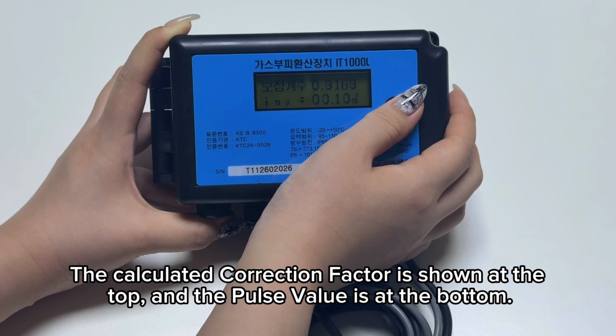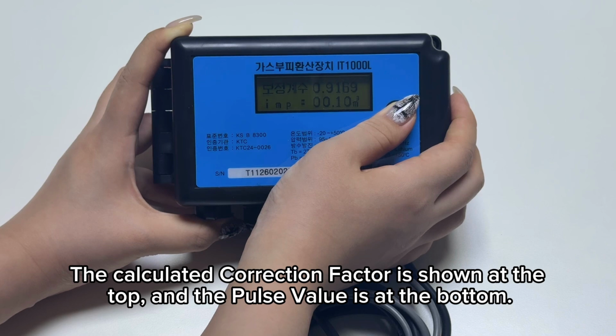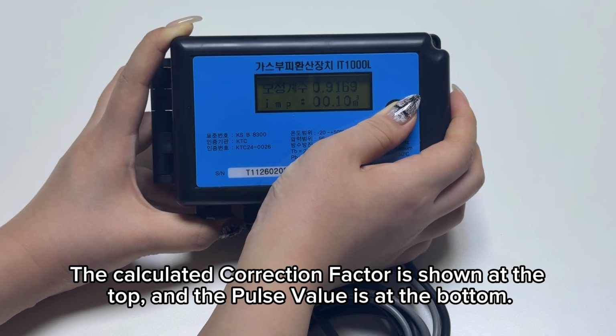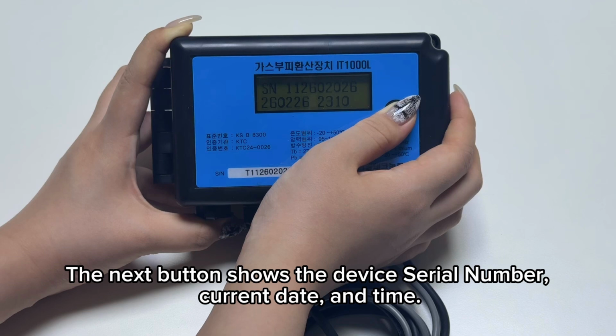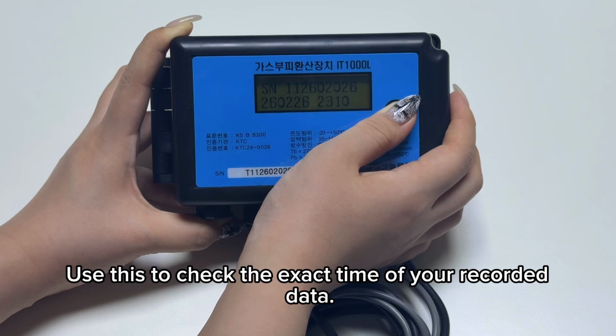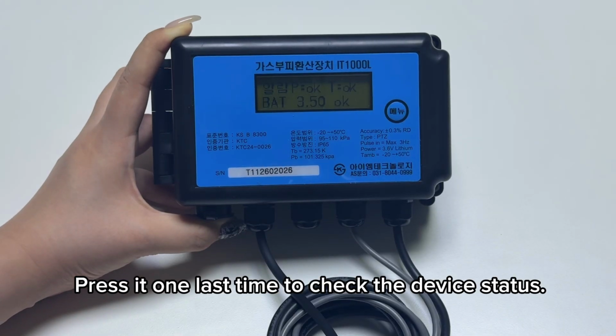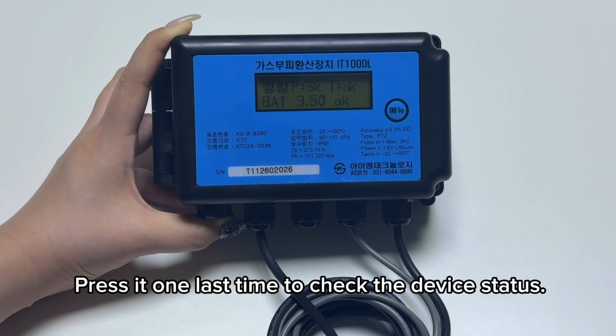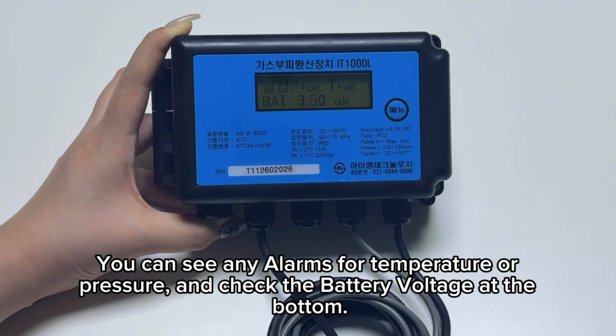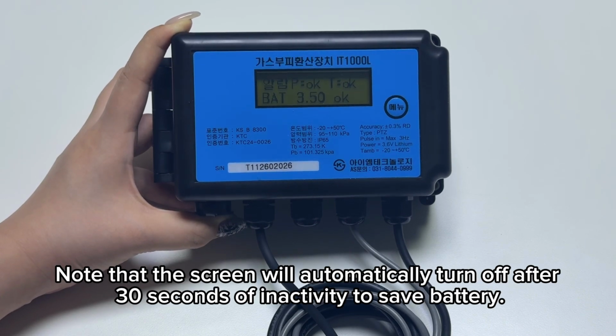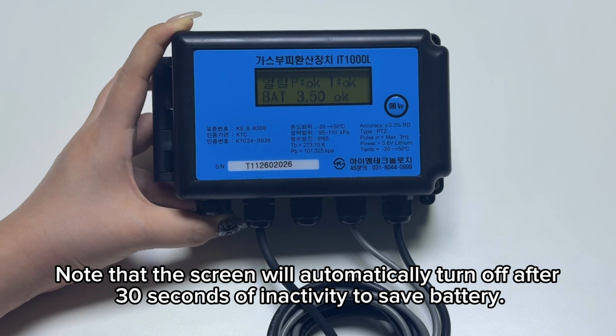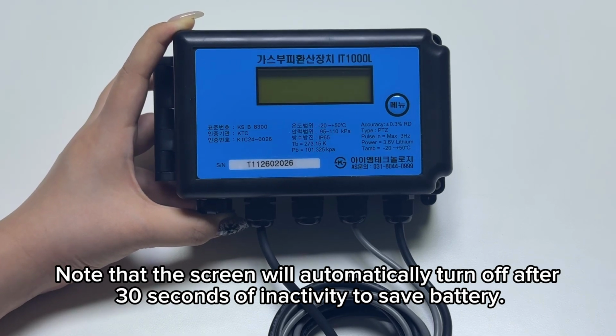The calculated correction factor is shown at the top, and the pulse value is at the bottom. The next button shows the device serial number, current date, and time. Use this to check the exact time of your recorded data. Press it one last time to check the device status. You can see any alarms for temperature or pressure and check the battery voltage at the bottom. Note that the screen will automatically turn off after 30 seconds of inactivity to save battery.